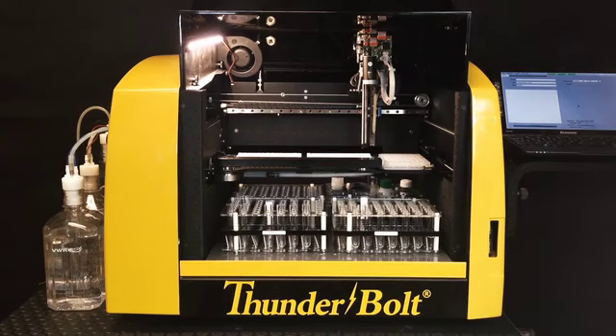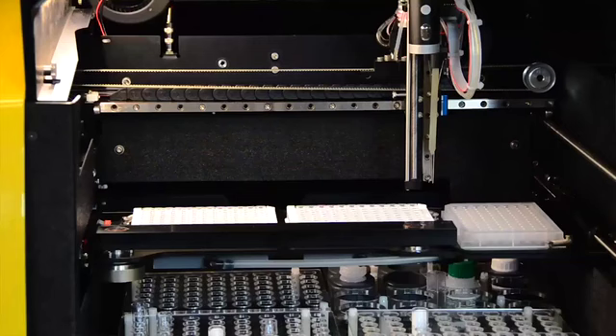Now, because we can dilute 1 to 100 directly into the well, we can do a lot of tests faster than many larger, bulkier, more expensive instruments. As well as the incredible power of our probe, we have an LED reader and a patented incubator and shaker that allows us to keep the footprint small. And once again, the benefits of an LED reader are that you don't have to replace the bulbs, you don't have to worry about the bulbs dying out, and you're going to get a much more robust product. With the shaker, we have an orbital shaker, which we've made to try to mimic any type of normal manual processing of an assay. And the onboard convection incubator allows for an even heating across the entire plate.